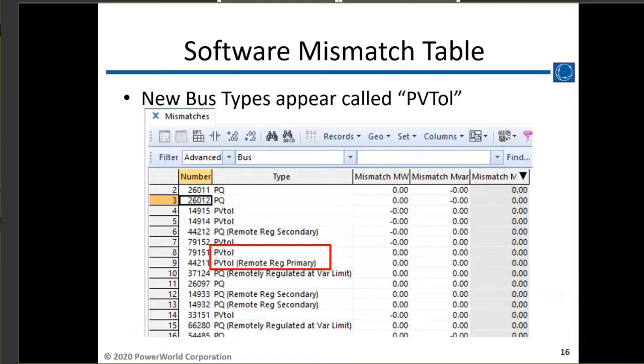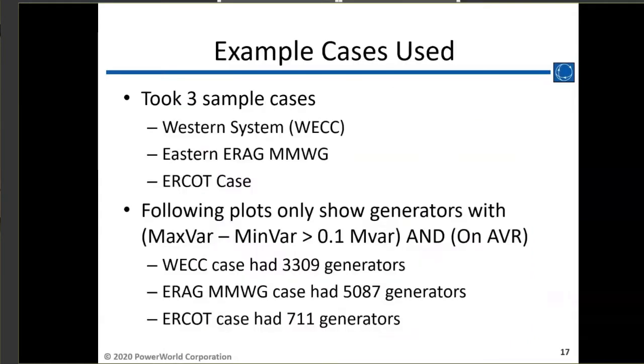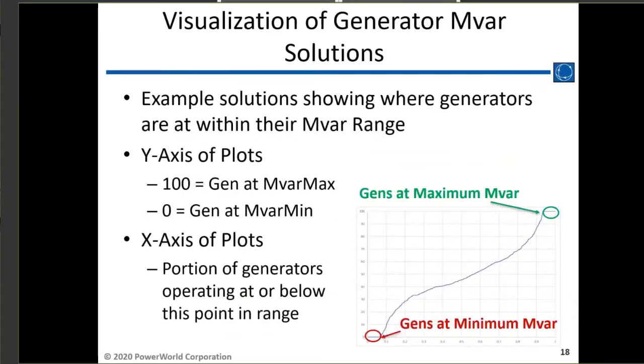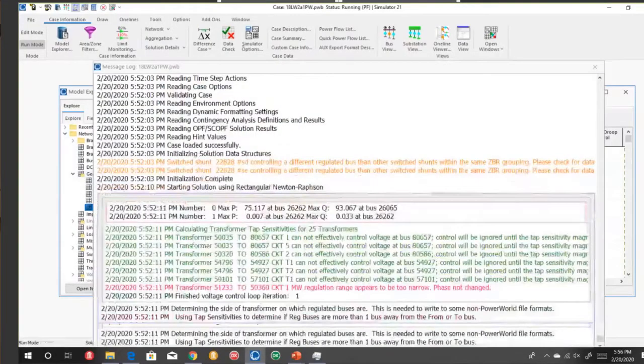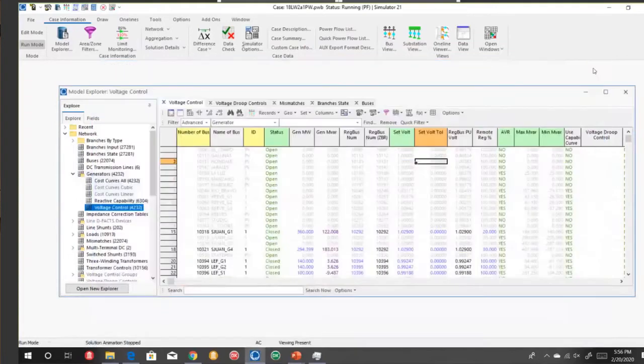but he's the first customer I've learned to actually use the feature. So I'll send you the ops file. And in the short run, did you find it useful? Did it move? Yeah, I was worried that it was going to fail the case. I've played with, say, a dozen cases. What I find is it's more stable. Most of the power flow failures are you fighting, trying to figure out which generators are at limits, and that's what's causing the problem, and this is making that better. I haven't had a chance to utilize it. I literally finished it last Friday. Correct.